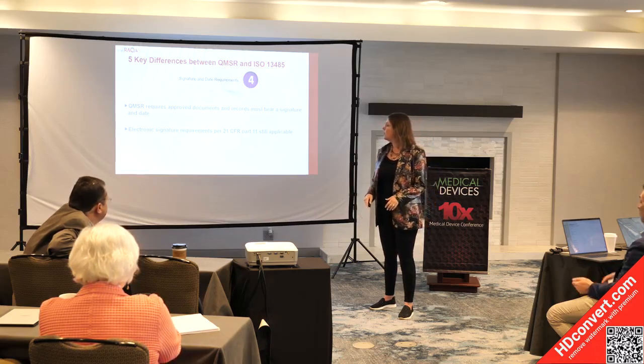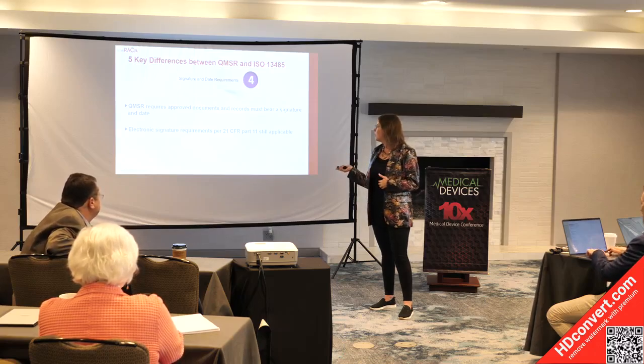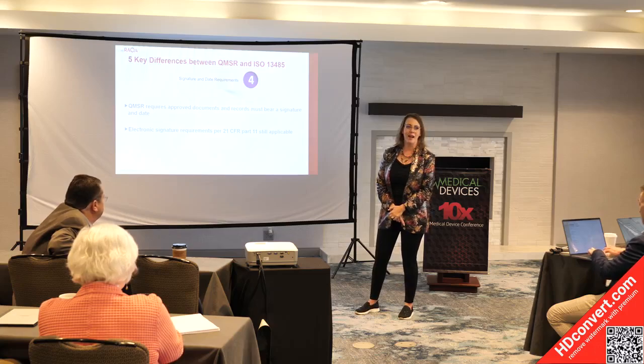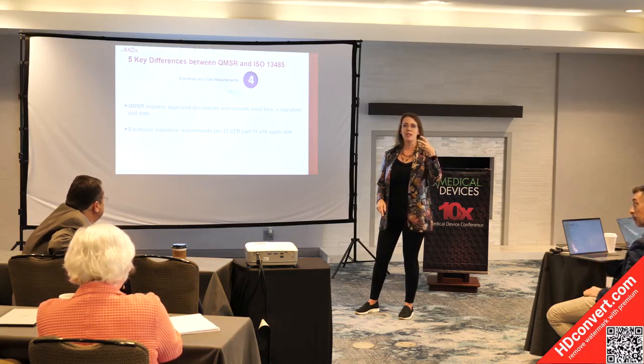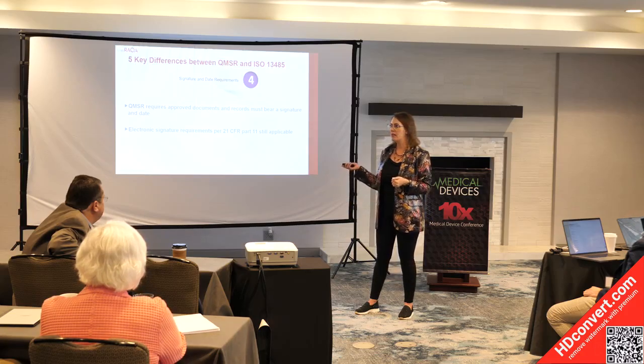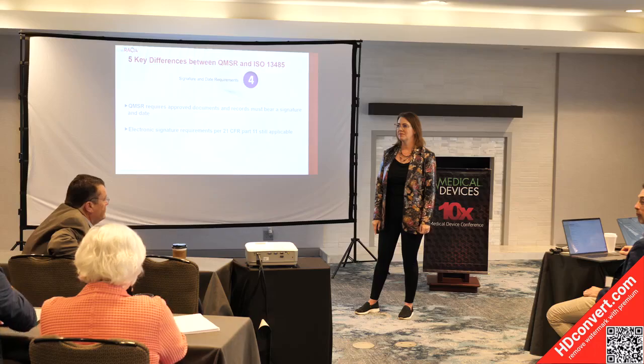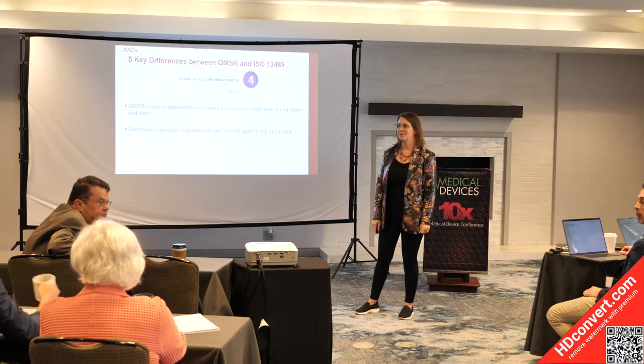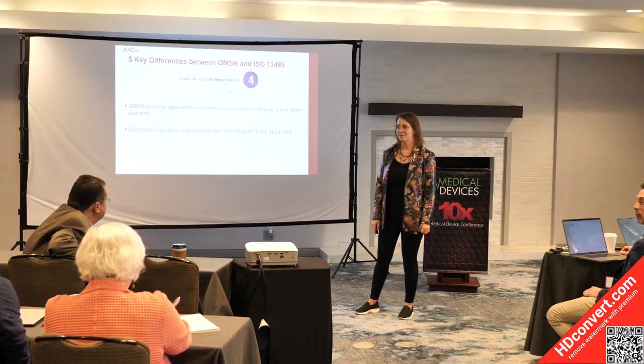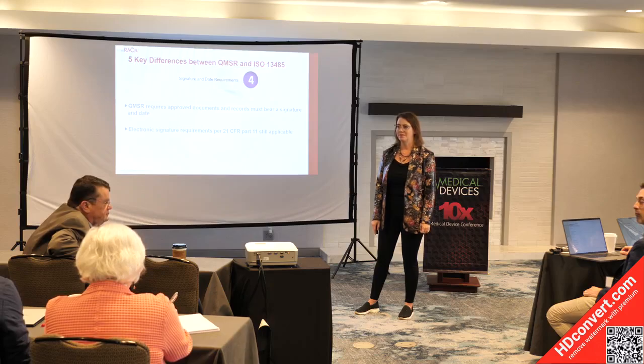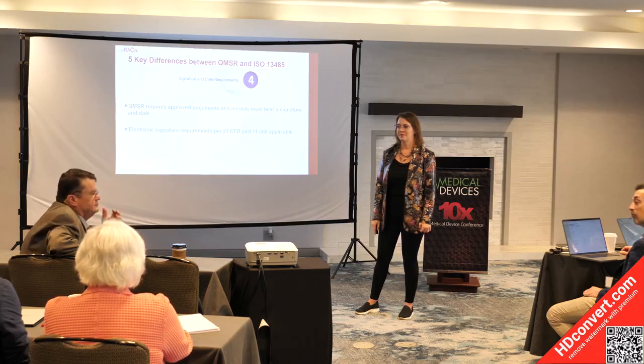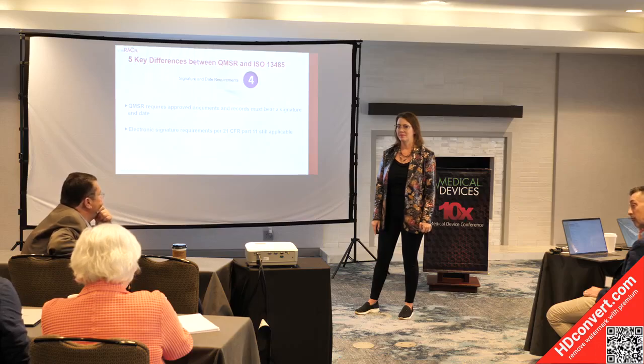For signature and date requirements, 21 CFR Part 11 will stay in effect. This is one of the few unique areas they retained in the QMSR, and you can expect increased FDA focus on it. I was with an FDA auditor and asked whether the risk-based approach for software applies to Part 11. She said: 'No — Part 11 is a law; we have absolutely no wiggle room.' FDA inspectors will cite you if you have not documented your validation strategy for Part 11.